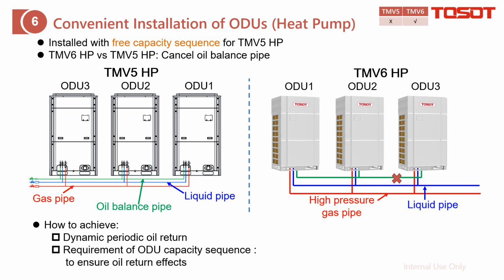For GMV5, it is free capacity sequence. That means we don't care about the outdoor unit capacity sequence. You can install in any capacity sequence, it's fine. However, for the GMV6 heat pump, as we need to ensure the oil can flow into each outdoor unit even without the oil balance pipe, we need to set up a rule, which is this one.